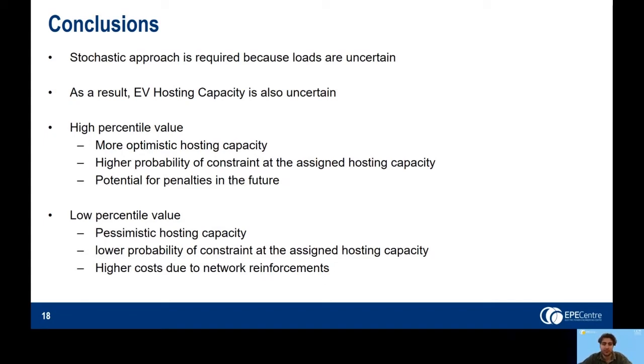When dealing with probabilistic results, choosing a high percentile value provides an optimistic hosting capacity, but this results in a higher probability of a constraint occurring at the assigned hosting capacity. On the other hand, choosing a low percentile value provides a pessimistic hosting capacity, but results in a lower probability of a constraint at the assigned hosting capacity.